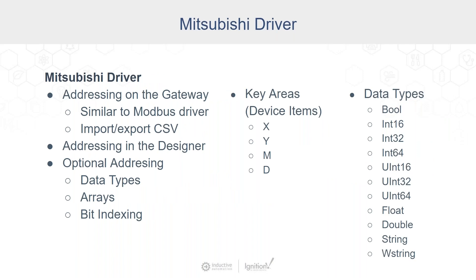Addressing in the Mitsubishi driver can be done in two ways: the first through the gateway on the addresses page, which is similar to the Modbus driver, where you can import user-created CSV files. Addressing can also be completed in a designer, following the OPC UA server node syntax.